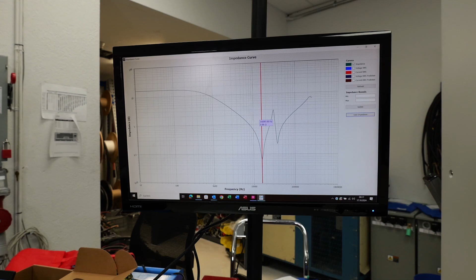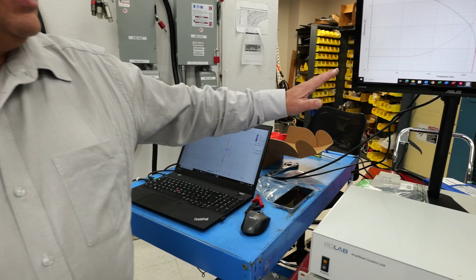That means in that range our current will go up to a very high range. If we want to see where it will go, we can activate here in this setup current RMS, and then we see exactly the red is our current. We see the lower the impedance, the higher the current. That is why the standards say that in the resonance range, where the current is exploding, it must be limited. On the other side, the standards say when there is a voltage drop at higher frequencies out of cable inductivities, this must be compensated. And we use this impedance curve for these calculations.